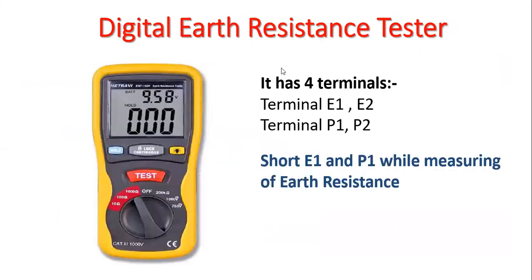Then next, the digital earth tester, or digital earth resistance tester. Basically, it has 4 terminals, E1, E2 and P1, P2. For the measurement of earth resistance for an 11 kV or 11 by 440 volt substation, we have to short the E1 and P1 while measuring. It has 3 ranges of resistance: 10 ohm, 100 ohm and 1000 ohm. We are measuring the value for the 11 by 440 volt pole mounted substation, so the resistance should be less than 10 ohm. That's why we have to select the 10 ohm range in this practical.